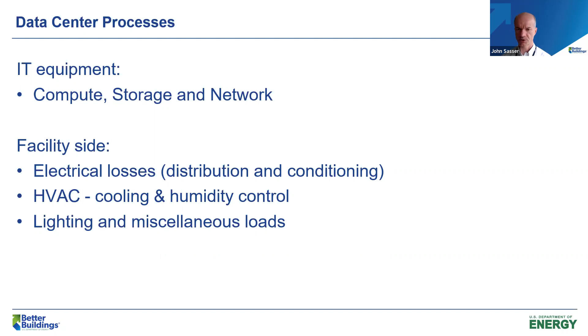Those UPS systems condition the equipment and provide storage for any brief power interruption. We also have cooling and humidity control - in data centers, it's really constant rejection of heat, with very little heating required since the servers provide their own heat. So you're trying to get that heat out of the facility to maintain appropriate environmental conditions in the data halls. And finally, there's lighting and other miscellaneous loads within the data center.